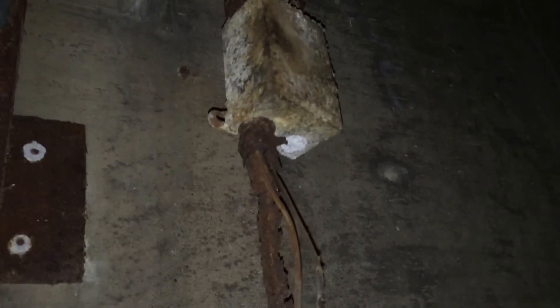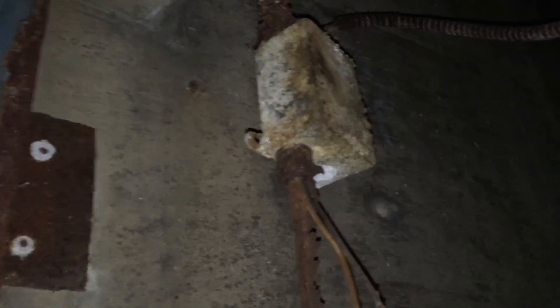What we have is a violation of section 110.11 — conductors and equipment cannot be located where gases, fumes, vapors, liquids, or other agents can have a deteriorating effect. And obviously that's what happened here: the lighting completely rusted out, the raceway is completely rusted out, the box is corroded, and the mounting means broken off because it's rusted.